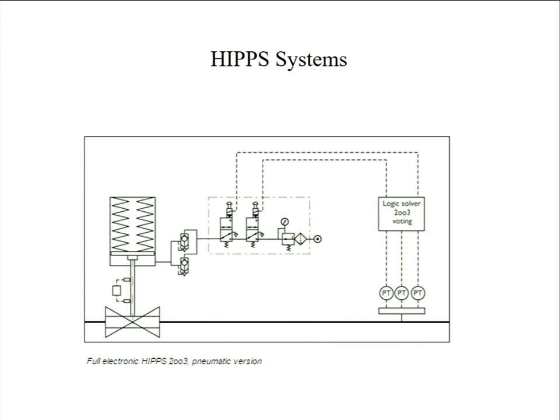Transducers and transmitters, the difference is a little bit academic really between the two, but what they are is basically means of converting typically pressures to some form of electrical signal. So you might get an analog signal, so it might be generating something like 4 to 20 milliamps, but it might also be a Modbus type, a digital value. There's all sorts of different types of ways of converting. A lot of them work on the principle of some sort of diaphragm movement. One to keep an eye on is whether things are defined as being gauge pressures or absolute pressures. And equally, you might be interested in just a single pressure measurement or a differential pressure.